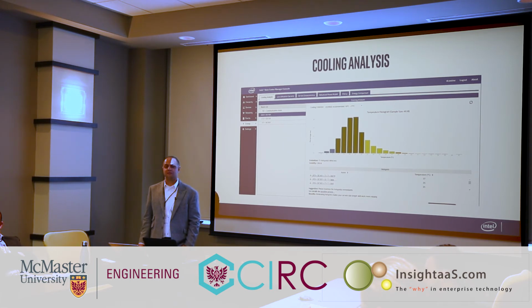I know it's a common perception, even in the research, that server consolidation is good, but we have found that when you turn off the server, you turn off the fan, and now it's not sucking air. So heat recirculates from the back, hot air to the front. What it does is heat up the front. So your cooling unit starts seeing the temperature going up and starts working harder, so you start spending more power on cooling. You're saving on the server part, but you're spending more on the cooling part. That's a good point, actually.